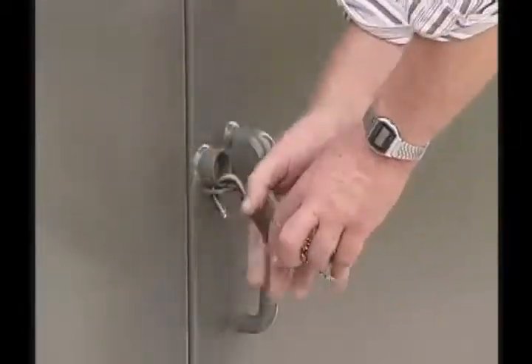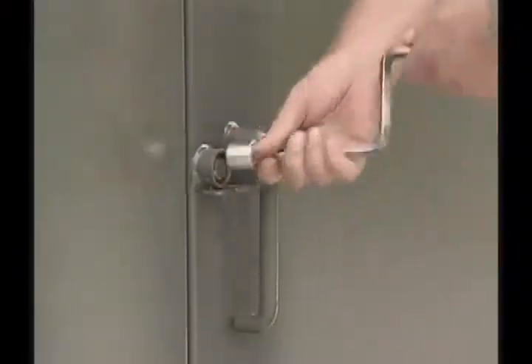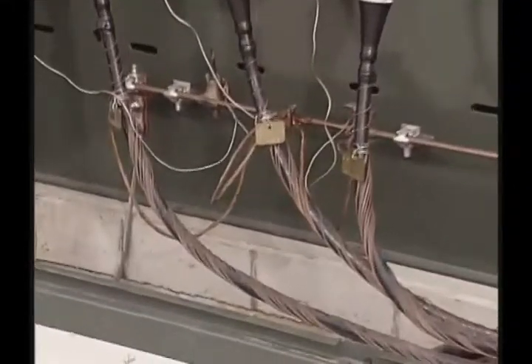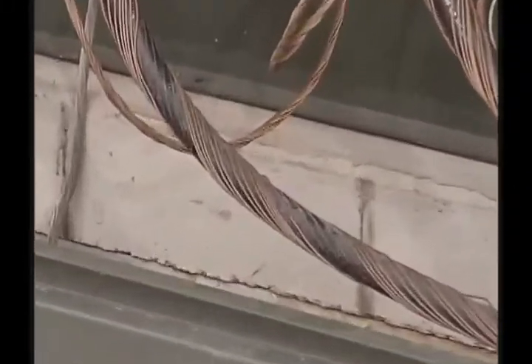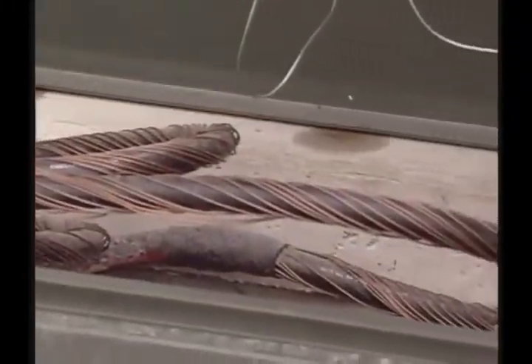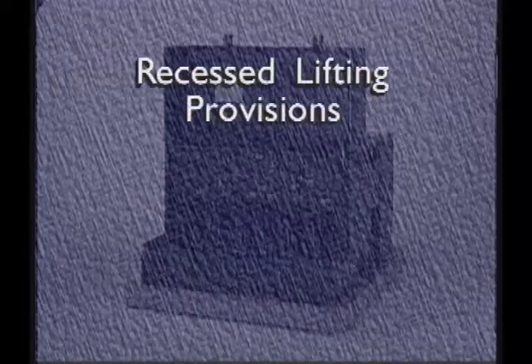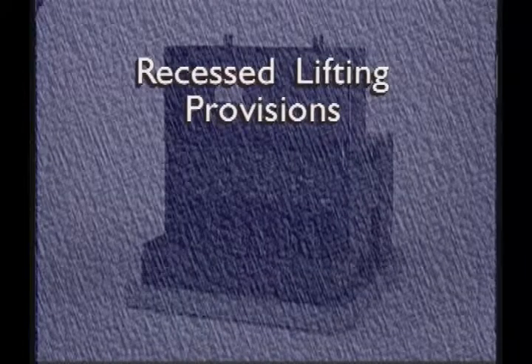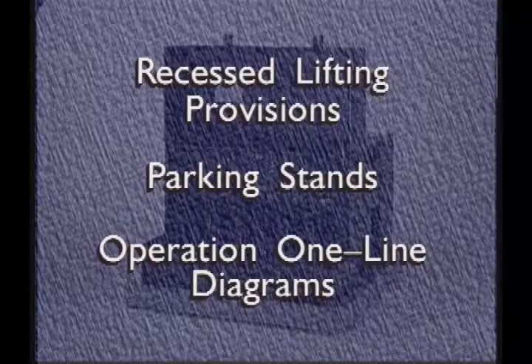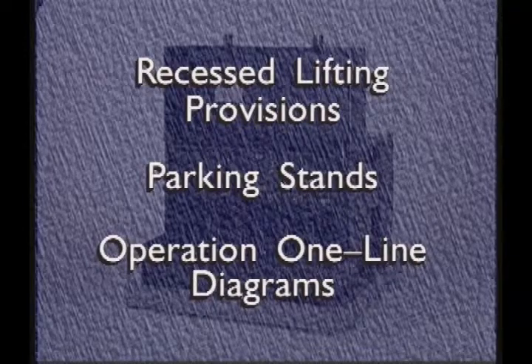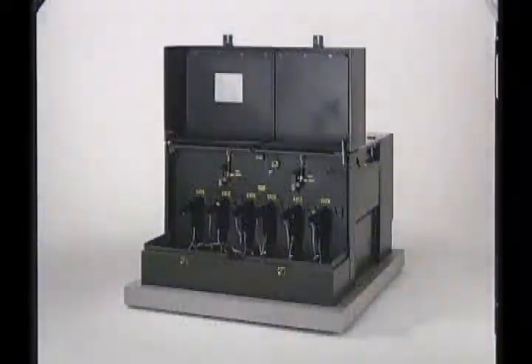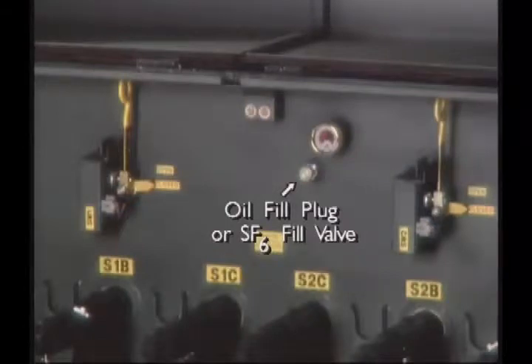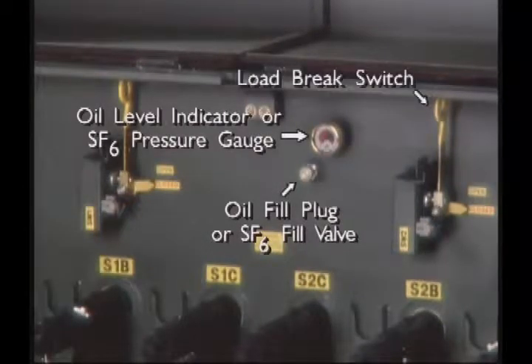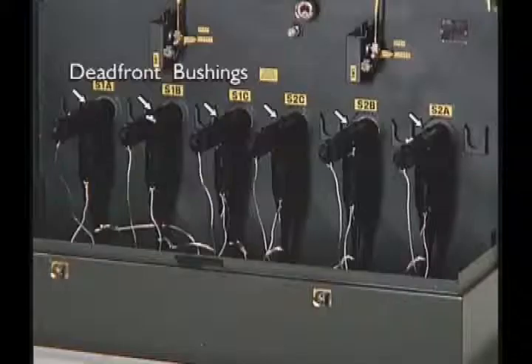The VFI has a padlockable cabinet, which should be locked at all times to prevent contact with hazardous voltage. Power is fed underground to and from the switchgear through openings in a concrete pad. The VFI has recessed lifting provisions, parking stands, and operation one-line diagrams. In this configuration, the source side has an oil fill plug, oil level indicator, load break switch, and dead front bushings.